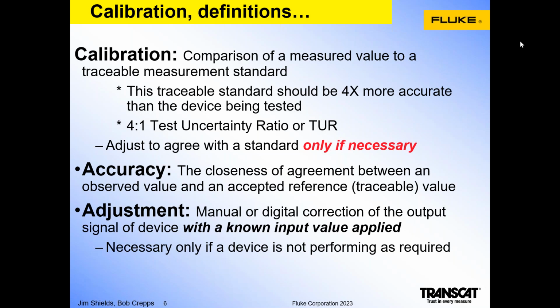to match requires a known input value to be applied. In other words, the input signal to the instrument before you make the adjustment needs to be a traceable source stimulus value in order to get the correct result. And again, adjustment is only necessary if the device is not performing as required. That brings up the topic of adjustment thresholds.